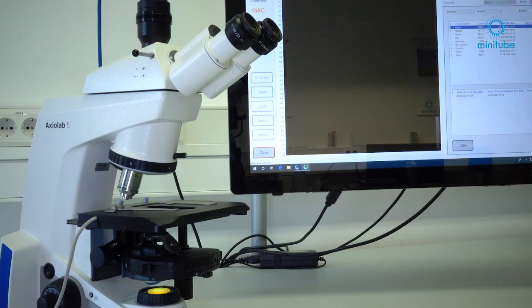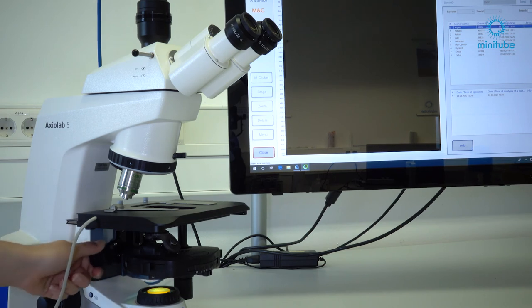What to do when no picture is visible? Please check if the condenser is at the right position. This is normally at the top stop.